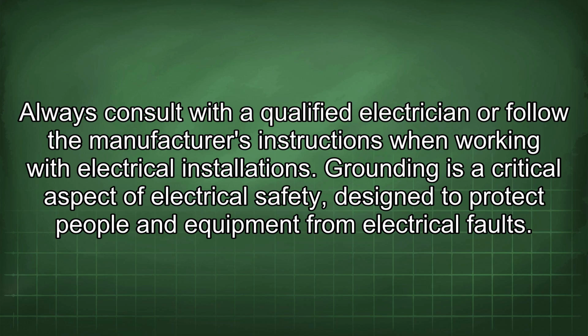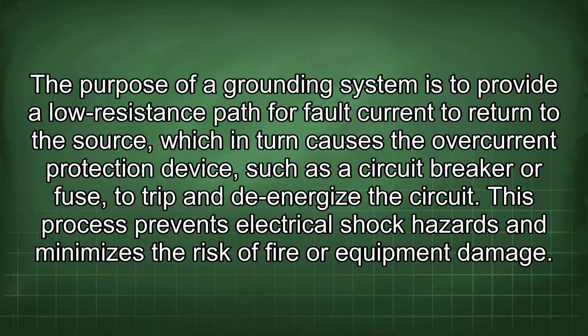Grounding is a critical aspect of electrical safety, designed to protect people and equipment from electrical faults. The purpose of a grounding system is to provide a low-resistance path for fault current to return to the source, which in turn causes the overcurrent protection device, such as a circuit breaker or fuse, to trip and de-energize the circuit. This process prevents electrical shock hazards and minimizes the risk of fire or equipment damage.